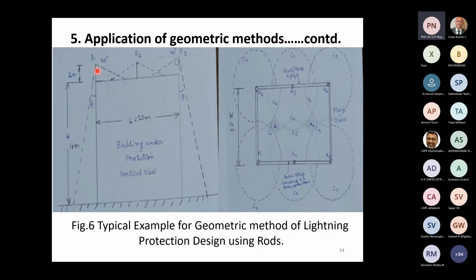From Table 2 of IEC, as I have shown you earlier, the protective angle is 70 degrees. So I draw a cone of 70 degrees. The area of this radius is protected by this rod. Now, at this corner, I have another rod of 2 meters height. This will protect an area of this radius. Now you'll see that this area and this area are protected, but you have this area which is not protected. So I provide one more rod here, same 2 meters height, 70 degrees angle. You will see that the two protected areas are overlapping, so that's a safer arrangement. Now the other interesting thing is to consider this height. This rod is effectively at a height of 16 meters plus 2 meters above ground. 16 meters is the height of the building, plus another 2 meters.